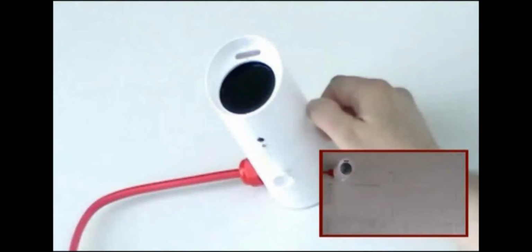Whenever the laser is on, the system will be in fault. The laser can also be turned on by using the laser switch on the receiver head while in the Engineering menu. We are going to use the thumb wheels to steer the laser in the receiver towards the transmitter. The laser is low-powered and flashes only once per second. However, it is a sensible precaution to avoid looking directly into it. It is not essential to steer the laser perfectly onto the transmitter. Within 6 inches is all that is required. If you cannot see the laser, refer to troubleshooting.